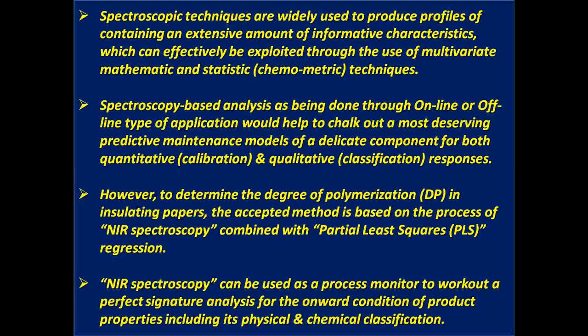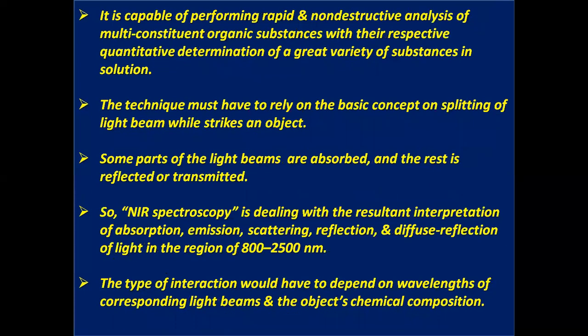To determine the degree of polymerization in insulating papers, the accepted method is based on NIR spectroscopy combined with partial least squares (PLS) regression. NIR spectroscopy can be used as a process monitor to work out a perfect signature analysis for the condition of product properties including its physical and chemical classification. It is capable of performing rapid and non-destructive analysis of multi-constituent organic substances with their respective quantitative determination of a great variety of substances in solution.